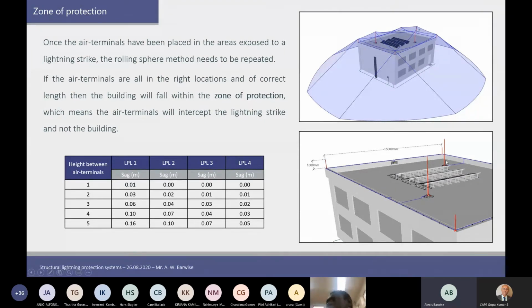So we are, in a more practical manner, applying the rolling sphere method by saying, okay, if the terminals are X meters apart, we know what the sag is. And so if the sag is, for example here, 0.1 meters, we should make our terminals, our catching rods, a little bit higher than 0.1 meters. And that's a far more practical approach that is able to be applied within the African continent. Here we can see on the top right again how it would look if one has to apply the angle method down to the side, and we've applied the rolling sphere method in between terminals.